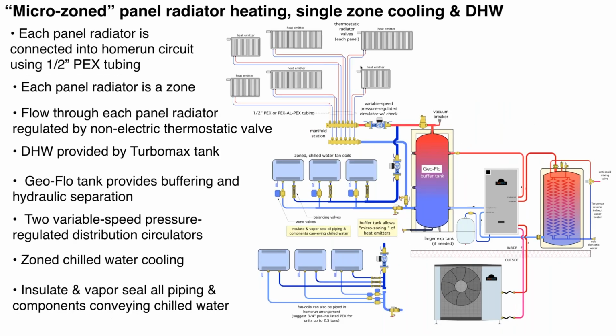Let's take it one more step. This time I'm going to go zoning on the chilled water side. So rather than a single air handler, these could be multiple small air handlers. They could be ducted. We've done projects in the past on large residential projects where we've installed maybe a 2-ton air handler in an area of a house, and did some ducting around it. And then in, perhaps, an area 100 feet away, there might be another air handler, again, some ducting around it.